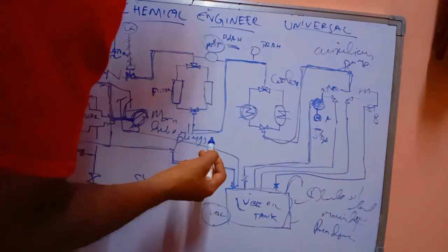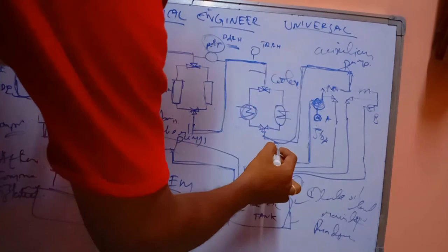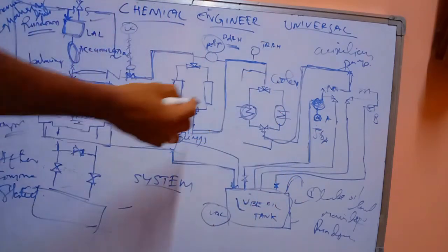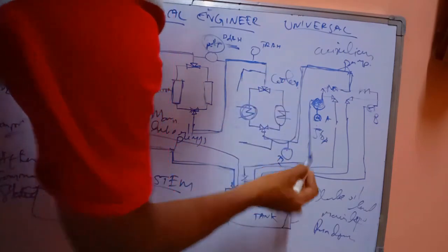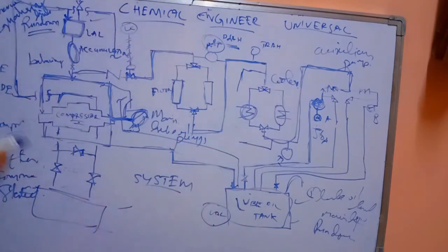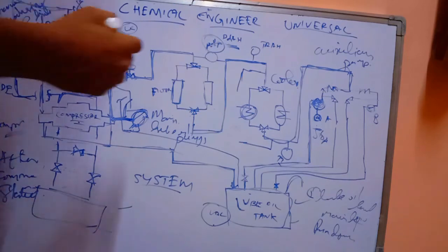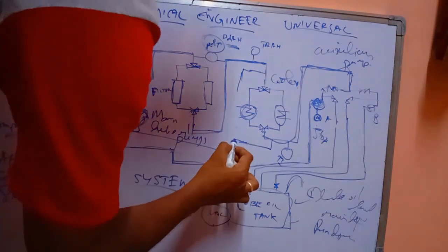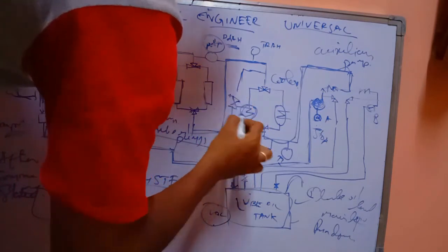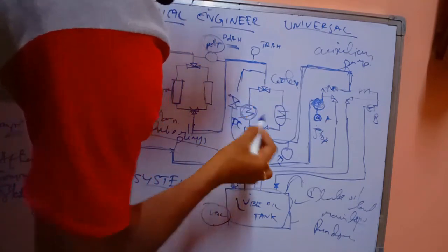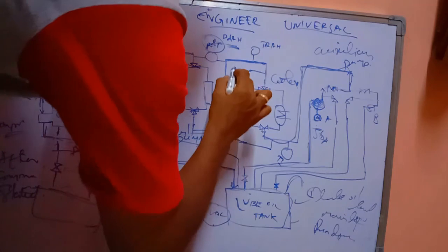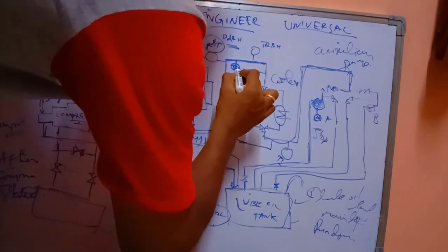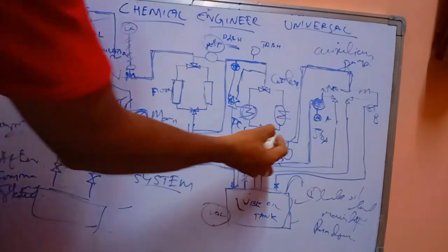And we have one more thing here. If we have more temperature, the oil is flowing through the system here. We have temperature gauges and temperature indicators. So we have already cooled the lube oil to whatever temperature we need, the set point. So we don't need to cool much. So we can bypass through a valve. This is called the TCV, temperature control valve. This will take the set point from the temperature indicator. So we can bypass this cooler also.